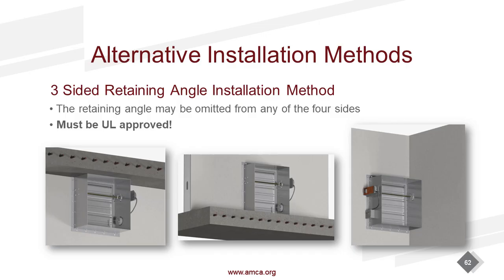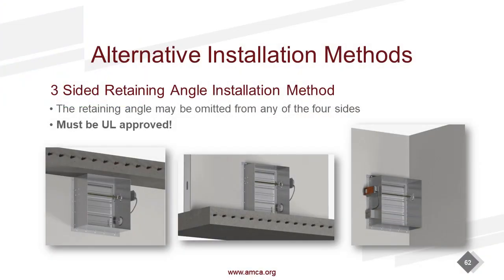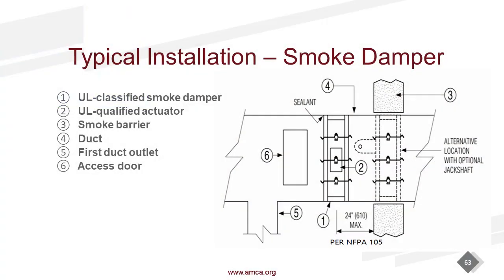Alternatively, that angle has to wrap around the damper on all 4 sides standard. You can get a UL approval for a 3-sided angle. Very special installations, but again, it must be a UL approved solution. If you are an installing contractor and you're tight to the ceiling, tight to the slab, tight to the wall, we're going to zip a screw right through the damper sleeve into that substrate and then put the 3-sided angle on. Some manufacturers have all 3 of these installations. Some have 2, some have none. If you have this condition in the field, call your damper representative and ask them for this instruction.